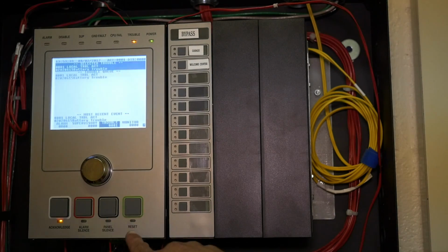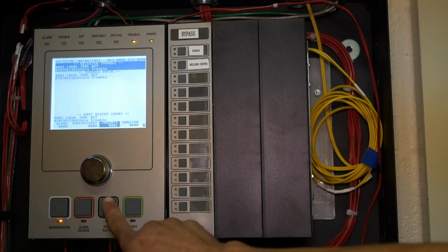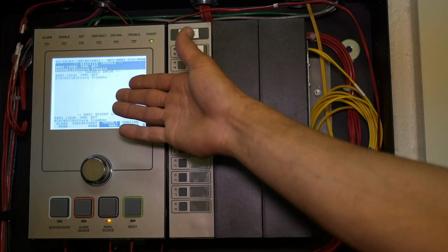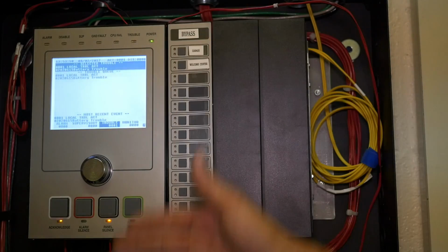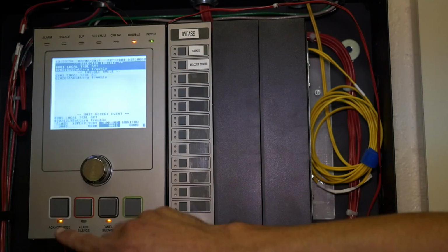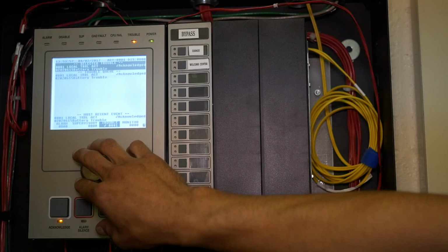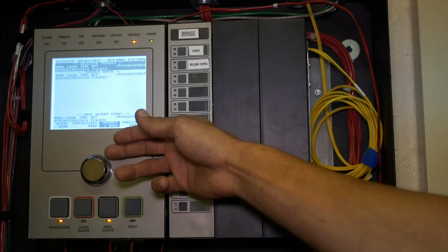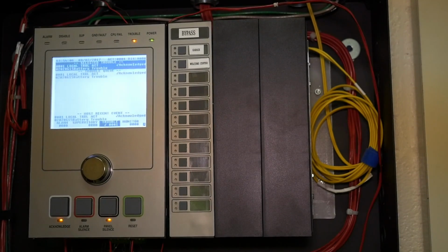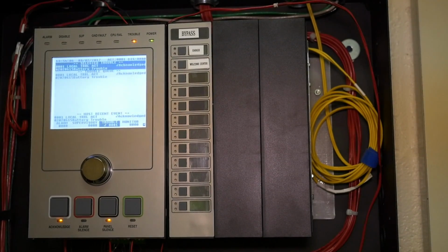So, same thing, your panel's beeping. Panel silence is going to stop it from making noise, so you're not just listening to that the whole time until you correct the issue. When a light is flashing, that means you have not acknowledged it. You might be able to see it on the screen because there's only one, but if there were 50 troubles, you would only be able to see 5 or 8 at a time, so you'd have to scroll through. Once you hit the acknowledge button, or physically scroll through if there were multiple, that light will go solid and let you know that you've acknowledged all the troubles or supervisories within that group.